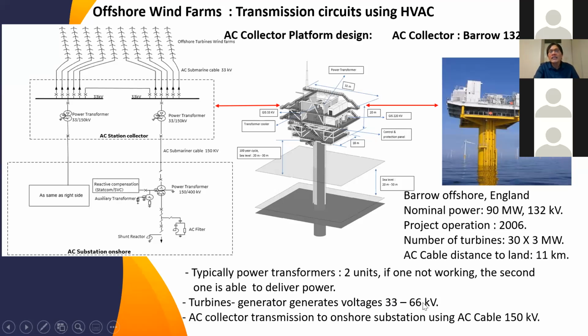So the highest turbine today, let's say Haliade-X, can produce up to 13 megawatt per turbine with the output voltage 66 kV. And here, typically for the power transformer, we install 2 because if one unit is not working, the second is able to deliver power.